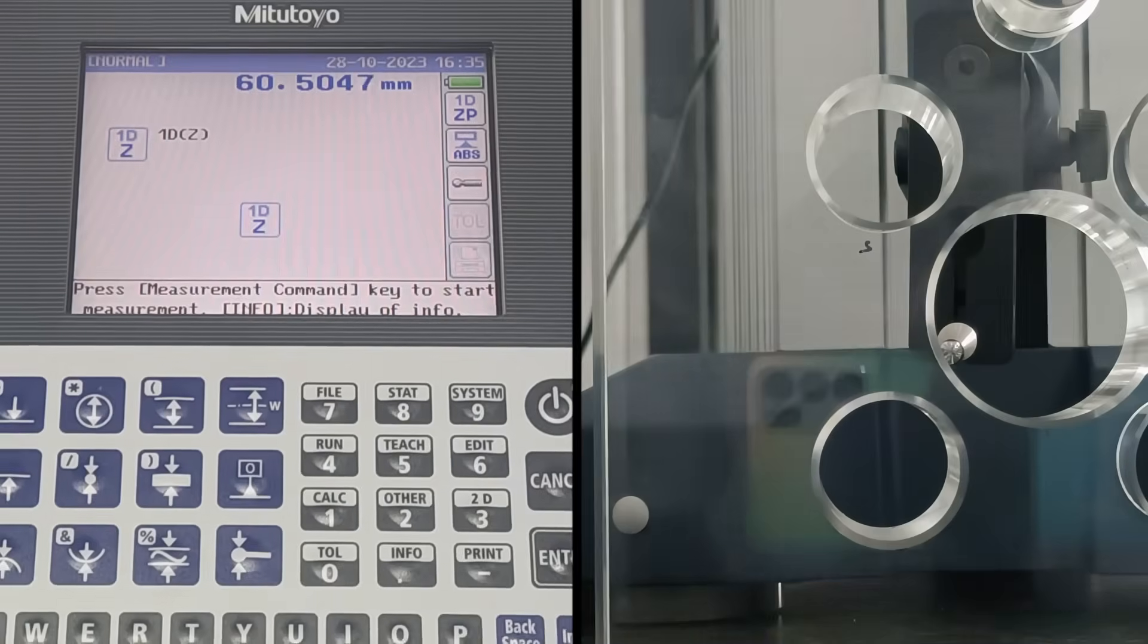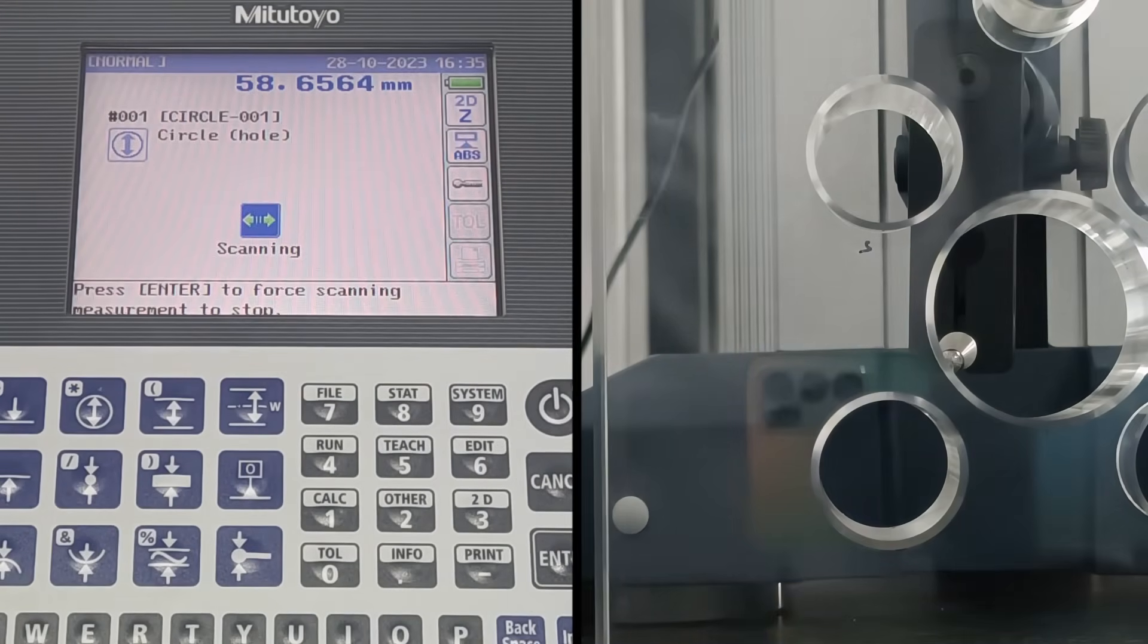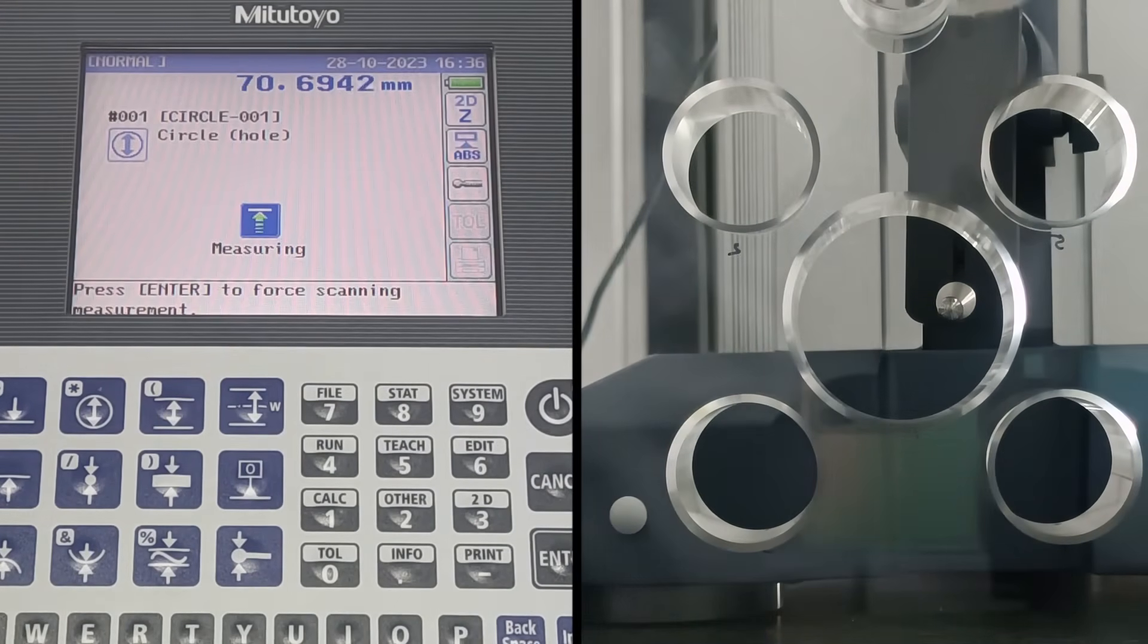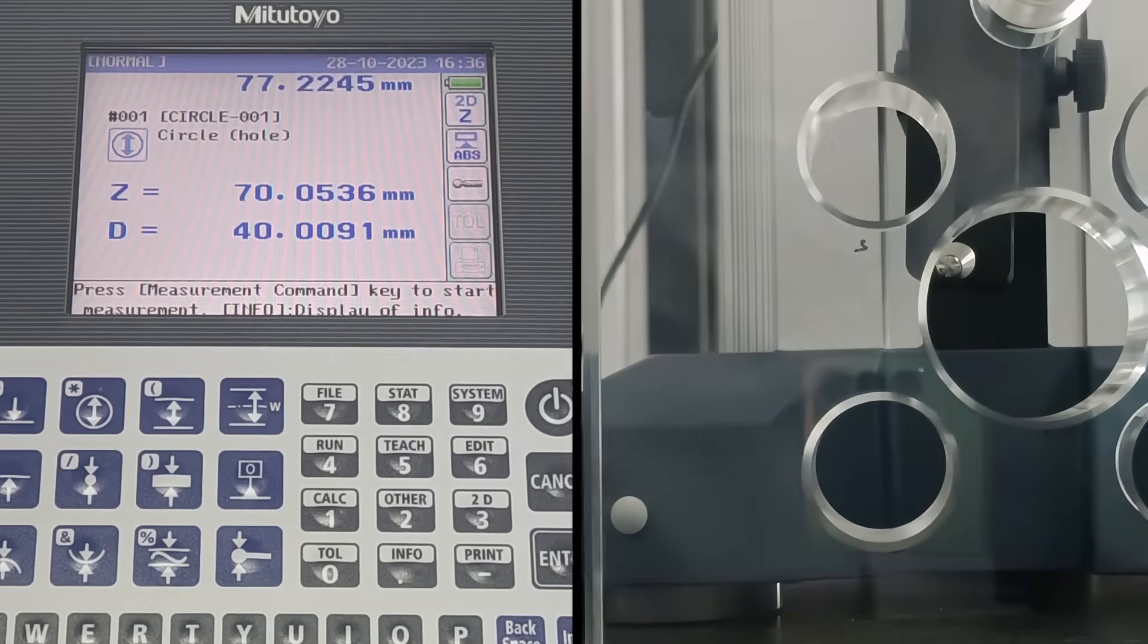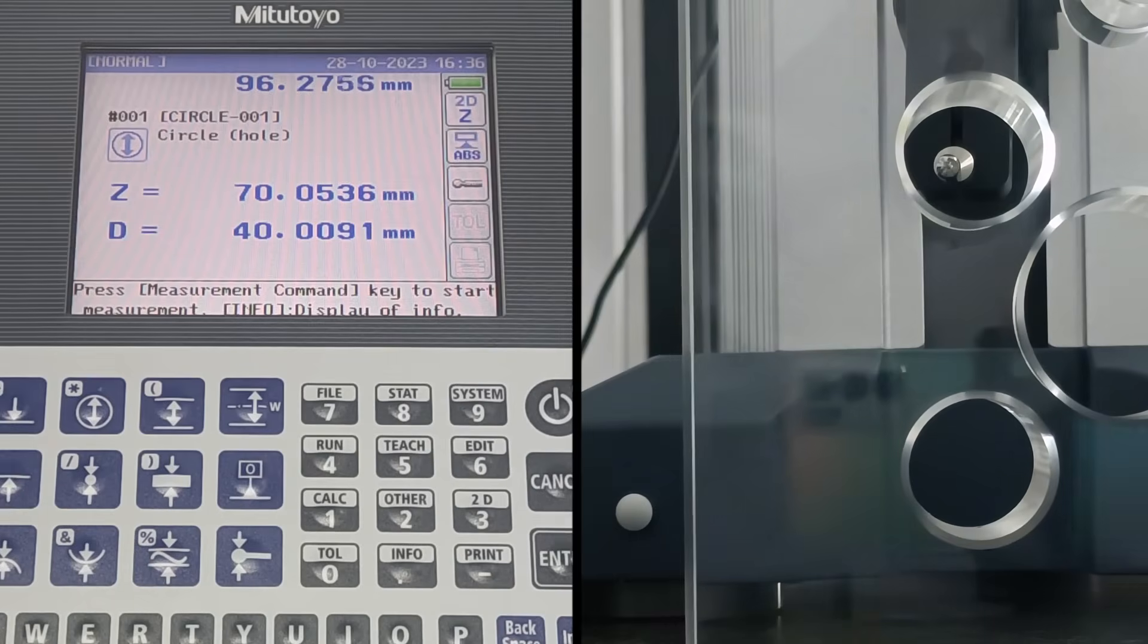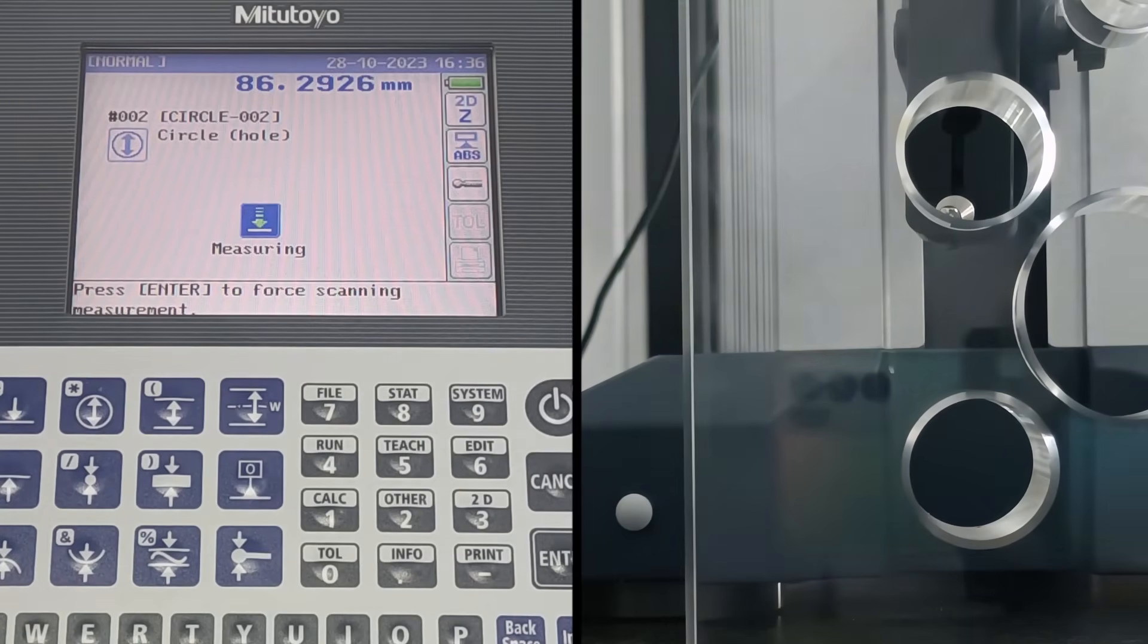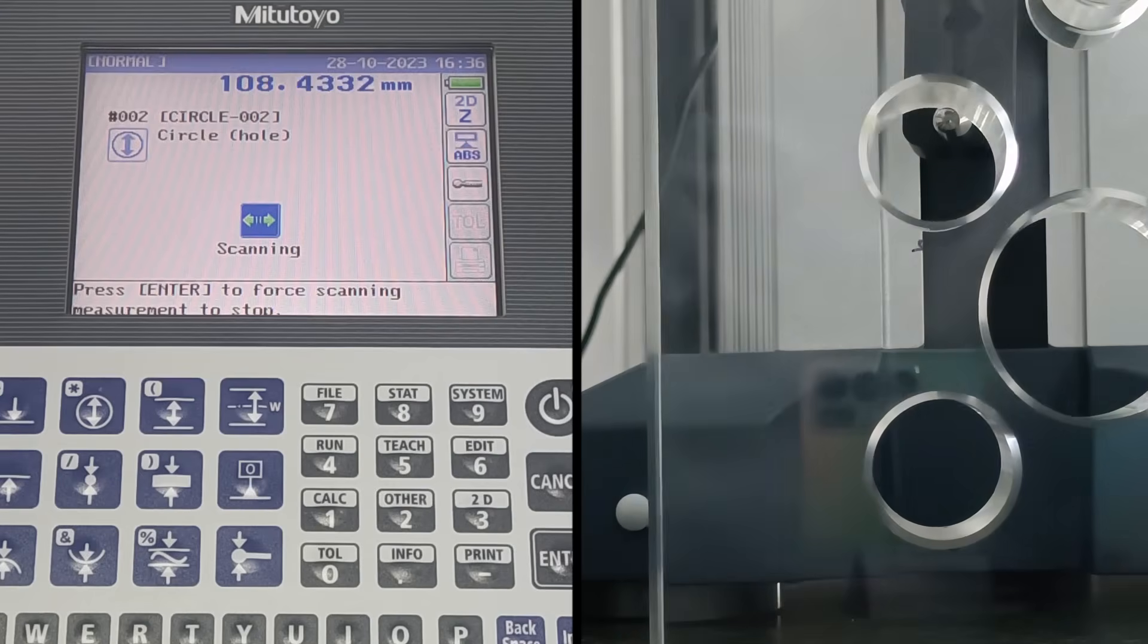The 2D sequence follows 1DZ, 2DZ, 2DX, 2DZX, and back to 1DZ. Measurement is done using 2DZ. Mark all circles to identify and measure one by one using diameter command. 2D analysis allows to combine Z-axis and X-axis measurement data to obtain measured results in 2D coordinates.